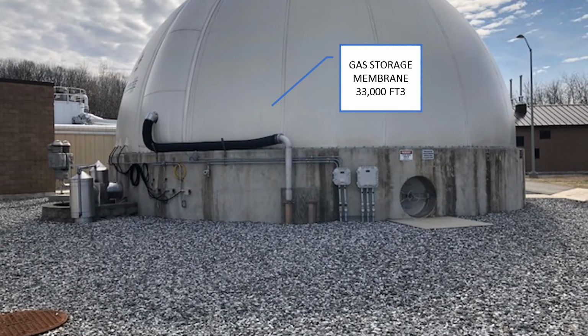I mentioned earlier, the gas wants to be utilized. It does want to go through additional treatment and go to either the boilers or our engines. However, if we're making more gas than can be utilized, the gas is going to back up and go into this gas storage membrane. The membrane can hold 33,000 cubic feet of gas, which is about 1/3 of our daily production of gas. The outer cover is fixed. There is an inner membrane that fluctuates based on the volume. And as I stated earlier, about 8 inches to 8¼ inches of water column can be maintained in here. Once that pressure is exceeded, this gas will start to flow towards our flare.